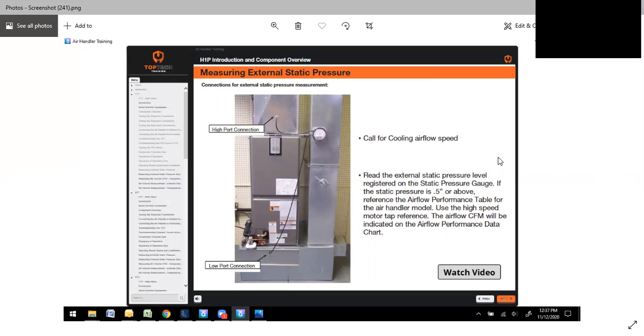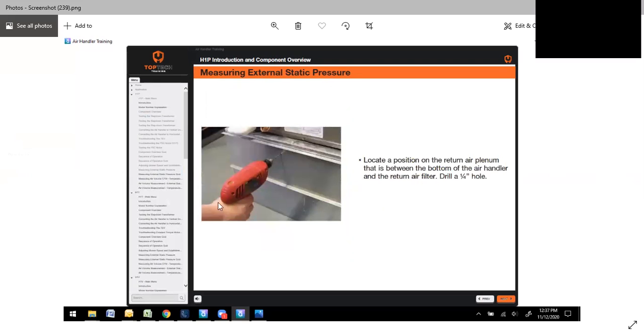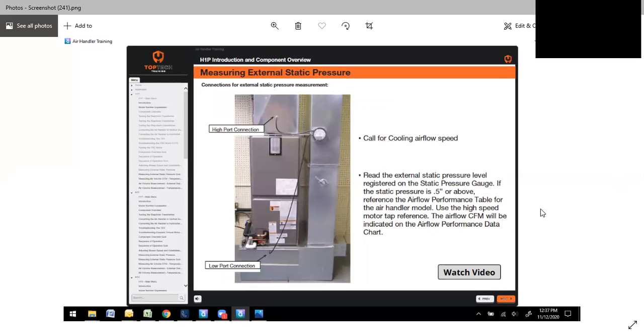Call for cooling. You can really check it in any speed, but what you're looking for is the worst case scenario, honestly. So call for cooling, which should be your highest speed. Read the external static pressure that's given on the static pressure gauge. If the static pressure is 0.5 or above, reference the performance table for the air handler. At that point, you can use either the high speed, but your static pressure is going to tell you basically how your system's breathing. This gets real important with X13s and ECMs, because as that static pressure goes high, 1 is really the max. As you start going above 1, you really start killing that unit.